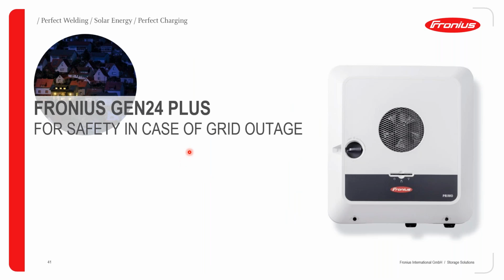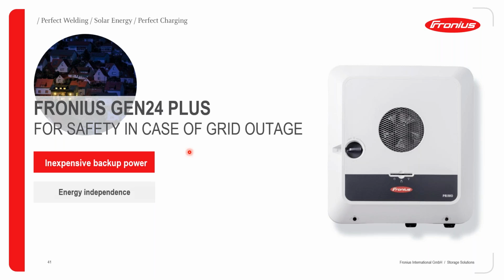When you come to safety in case of grid outage, the Gen 24 is able to give you inexpensive power backup. As I had mentioned before, the Gen 24 can give you what you call opportunity power using the PV point. And this PV point works with or without a battery system. So all you need is PV connected to your inverter. And as long as the PV system is generating power, if you do encounter a grid outage, then the PV point is powered up, and therefore you have opportunity power through the PV point.